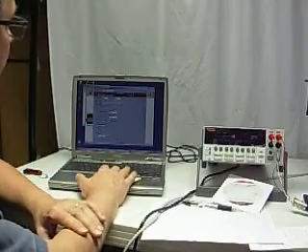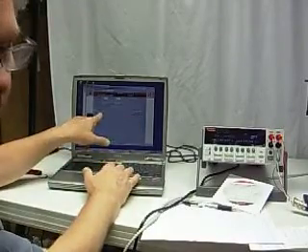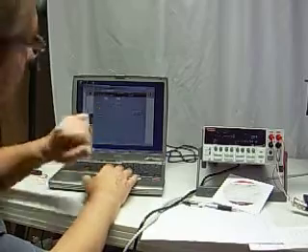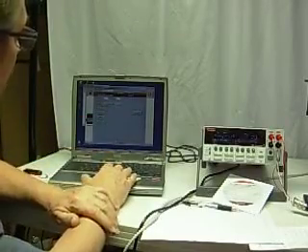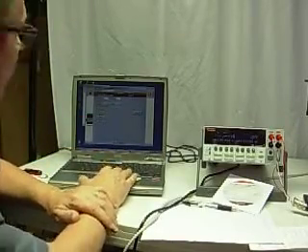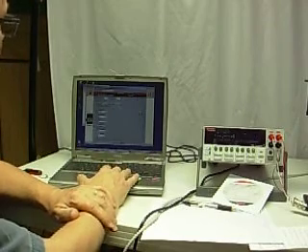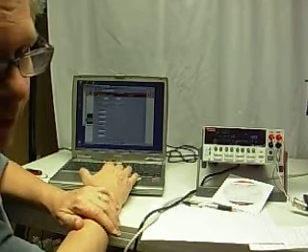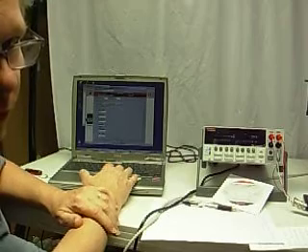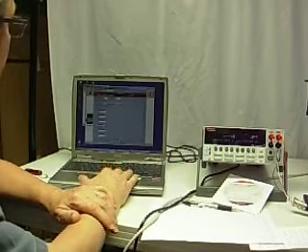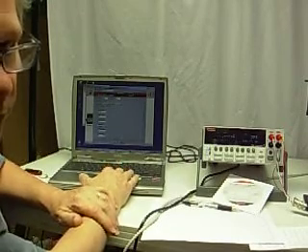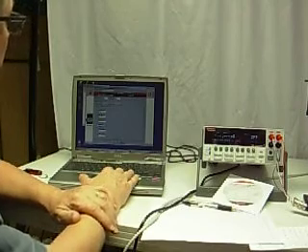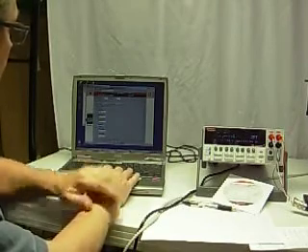In the advanced tab, you can select the four-wire measurement yes, in this case, and for SMU auto zero, always. So, we'll return back to the source. We've put minus 0.05 volts for the start voltage and 0.6 volts for the finish voltage, and that should be good.